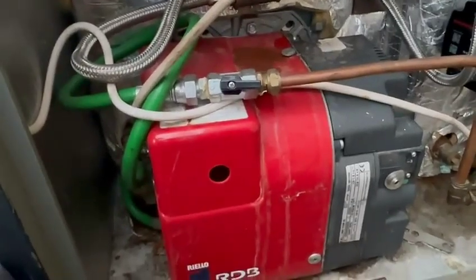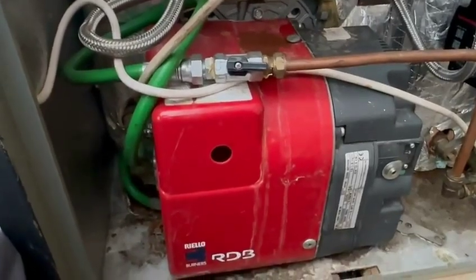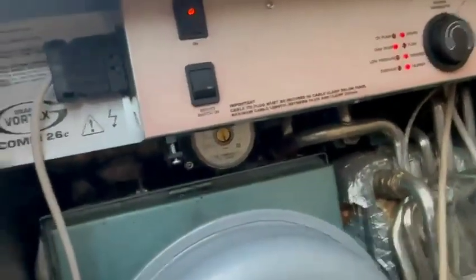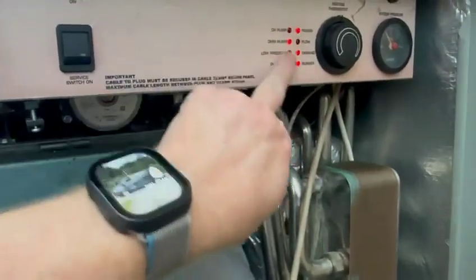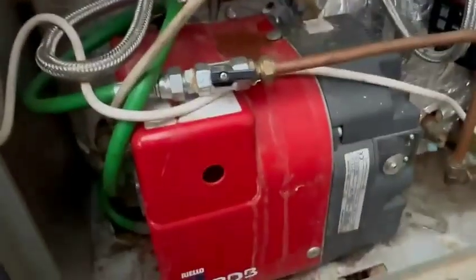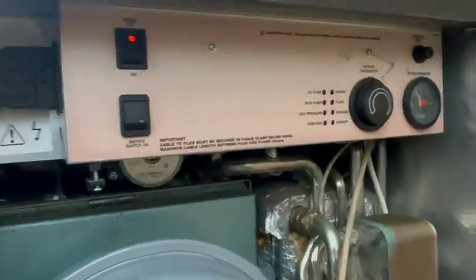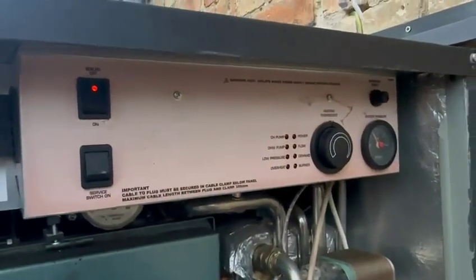As I've just spoken to you again now, the burner light's gone on and off as well. Okay, so the reported problem with this boiler is, one, it doesn't go, which is what it's doing here, and number two is that it was dead and doing nothing at all until they turned the mains power off and on again, and then all these lights were doing all sorts of weird stuff. So at the moment they've settled down, but they were messing around a minute ago. So that's telling me, one, I need to look at the burner and sort that out, so we'll turn it off. When I've sorted that out, number two, I need to find out why it's messing around up here. I'm going to guess it's probably going to be the PCB board. But anyway, let's get it to bits and have a little look.